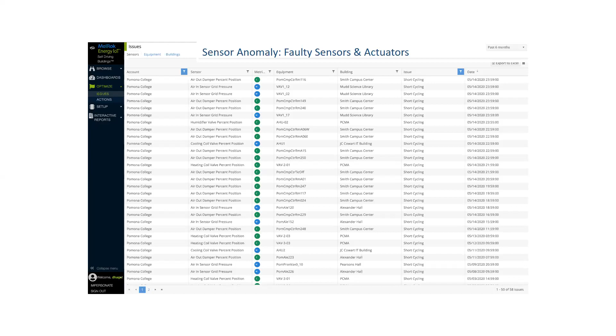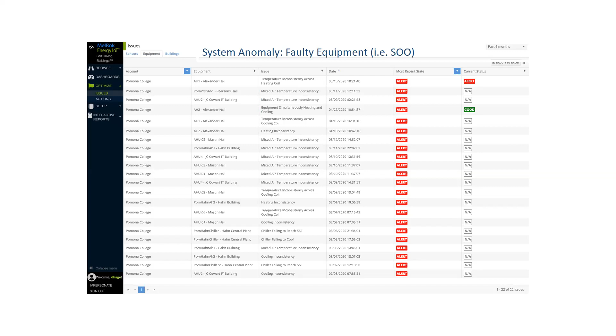Similarly, there's a system anomaly page. This is again where you're looking at a system, not just the sensor or the actuator. In here, one example would be simultaneous heating and cooling, and we had a ton of that. So again, here we turn them into work orders, and we go in and change the programming, or we do whatever we need to do, fix actuators, fix sensors, to get our buildings running more efficiently. Next slide, please.